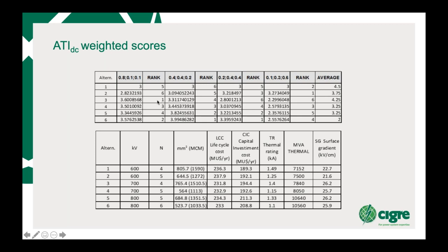Now, the one that scored best was really your option 6, because it gets a rank of 2, 1, 1, 4, and the average gave you a rank average of 2. And that option 6 was a 6 bundle 800 kV line for this particular load. So if you're using 3,000 megawatts over 1,700 kilometers, you're likely to be far better off with a 6 bundle 800 kV design. So this can actually help you determine voltage, bundle, etc.